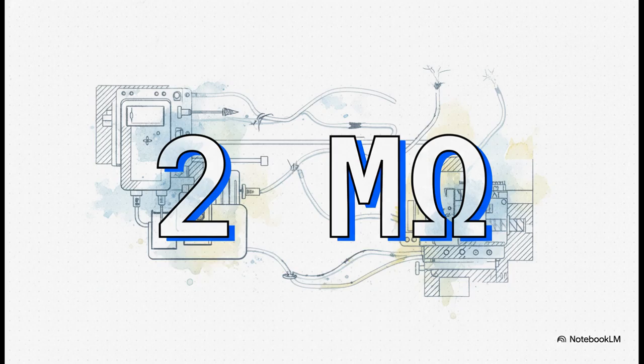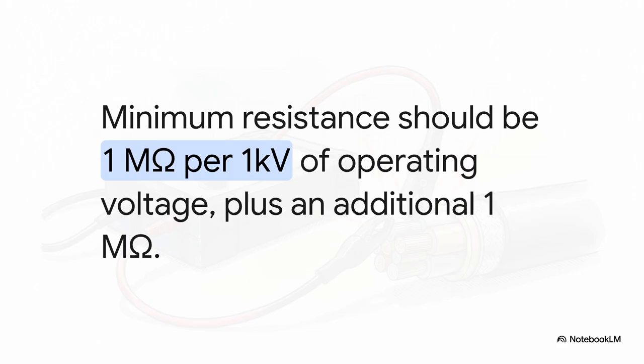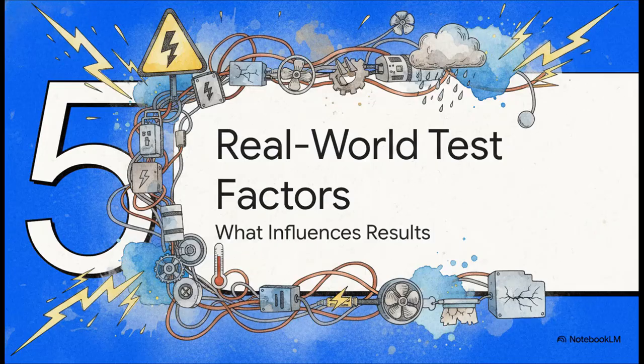Okay, now I want you to lock this number in your head. 2 megaohms. It's a key part of a really handy shortcut. There's this great rule of thumb you can use for a quick check in the field. The bare minimum acceptable resistance is 1 megaohm for every 1,000 volts of operating voltage, plus an extra 1 megaohm just for a safety buffer. So for a 1,000 volt or 1 kV system, the absolute lowest reading you'd ever want to see is 2 megaohms.